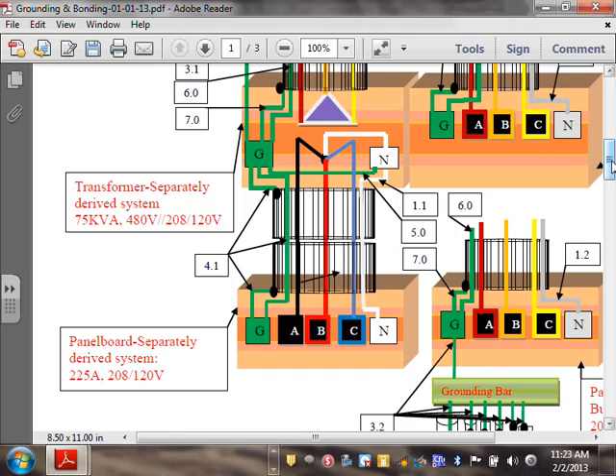So I have number 4, add the three number 4s together. How do you add them together? You have to convert them into kcmil, and then add them all together, and then you size the main bonding jumper. Or you go directly into each one of these panels and you bond inside the panel. Then you don't have to go higher than number 2.